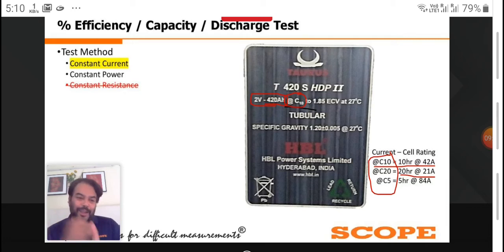You need to maintain the voltage, you need to maintain the charging condition, you need to see what is the state of health, what is the capacity remaining, all these things. So that is actually not maintenance free. None of the batteries are maintenance free from that angle. The only maintenance free aspect is that putting in the electrolyte, that maintenance is tension free. We are tension free from that. That's the reason the word came to the surface, maintenance free batteries.